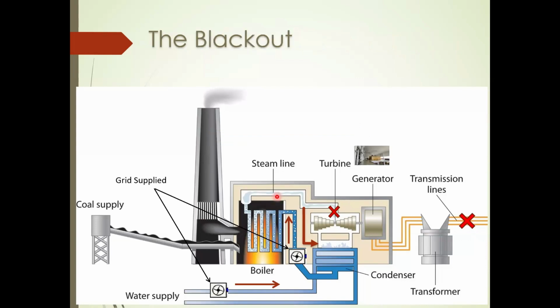Now, in a blackout, even though the power plant opens this generator circuit breaker, you won't have power to the 6 kV equipment, so these two pumps and all of their auxiliaries will lose power, and you have no choice but to stop these pumps from working. So grid supply will not be available. This cooling water pump will not be available. So cooling water flowing to the condenser will not be available. That means the steam will get trapped here and the pressure will increase here.